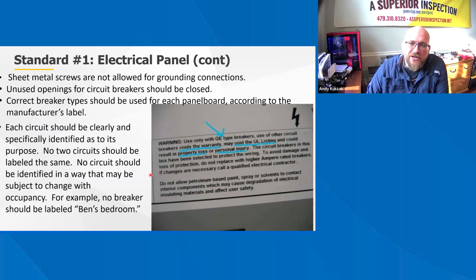If changes are necessary, call a qualified electrical contractor. And then two terms that you should keep in mind when evaluating the electrical system. An outlet is a point on the electrical wiring system where electrical current is taken to supply equipment. An outlet can be a wall receptacle, a light fixture, a smoke detector, or an appliance. A wall switch is not considered an outlet since no current is taken at the switch. Current is simply passing through.